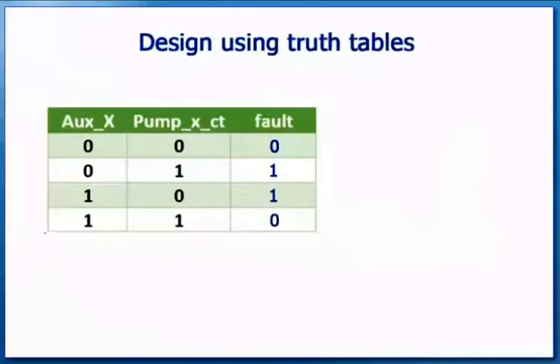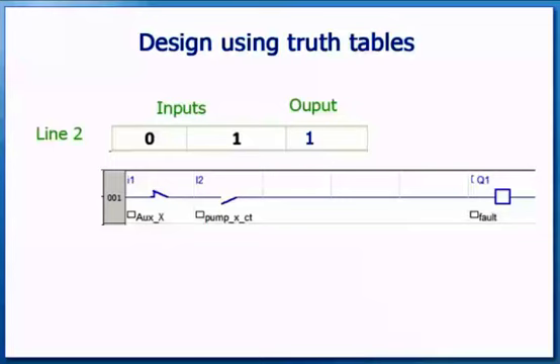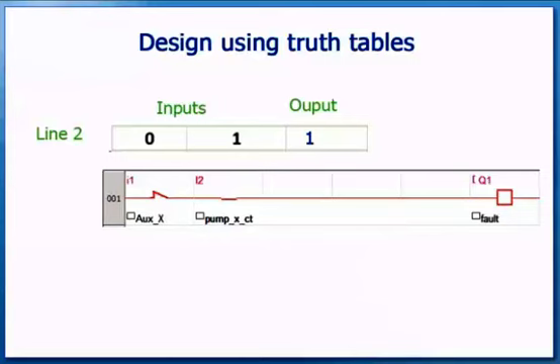With this method we can use the truth table to design our program. Focus on the conditions when the output is on — there are two that are true. For line 2: fault is on if auxiliary X is not on AND PUMPXCT is on. Using a normally closed auxiliary X and normally open PUMPXCT, this line will be true. This only works for the condition when auxiliary X is off and PUMPXCT is on.